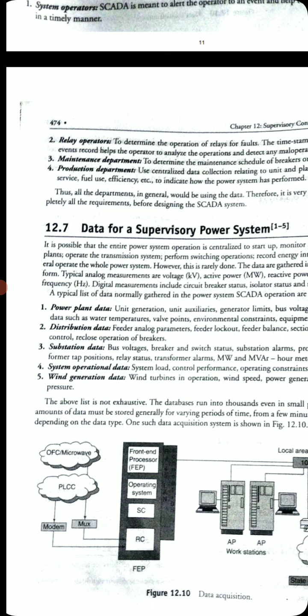Coming to the distribution data, it has the feeder analog parameters, feeder lockouts, feeder balance, sectionalization operation and control, and reclose operation of the breakers. All these come under the distribution data, because all these are at the distribution side. Coming to the substation data, it consists of bus voltages, breaker and switch status, whether the switch is on or off and the breaker is in on or off state, substation alarming, protection status, transformer tap position, whether it is in positive tapping or negative tapping, relay status, alarming of transformers, megawatt and megavar, that is the active and reactive power, and hourly meter readings. All those things are called substation data.